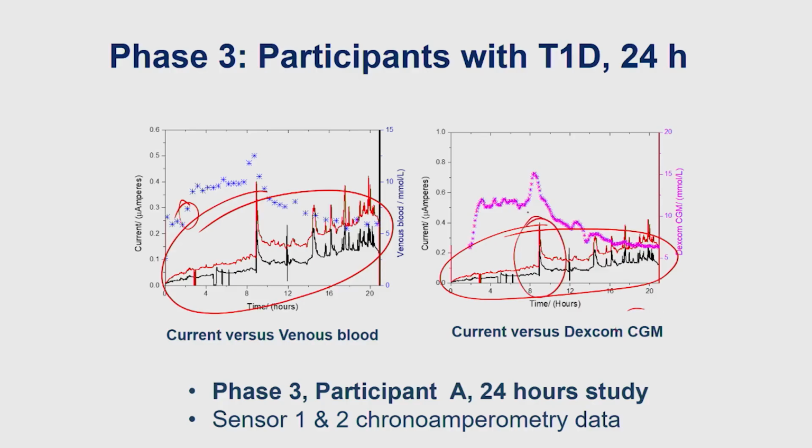You can see that we have a good correlation of the events, showing that the devices are performing as we need. Remember one thing: when you have your wearable sensors, you are not measuring glucose, you are measuring current. You have to then take that current and correlate it to the glucose if the events are matching. And that's what we're going to be learning as part of the case studies as well.